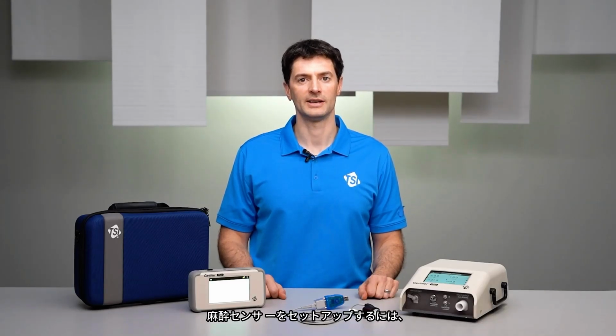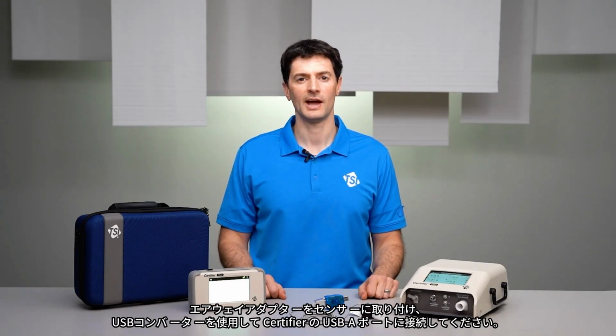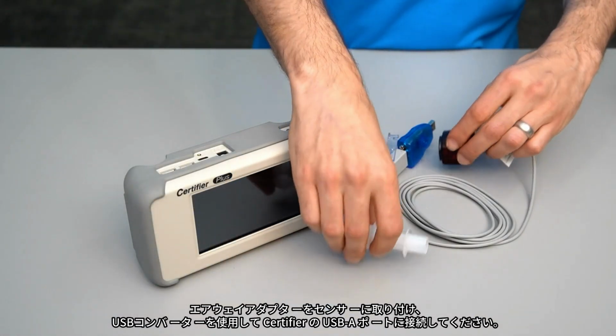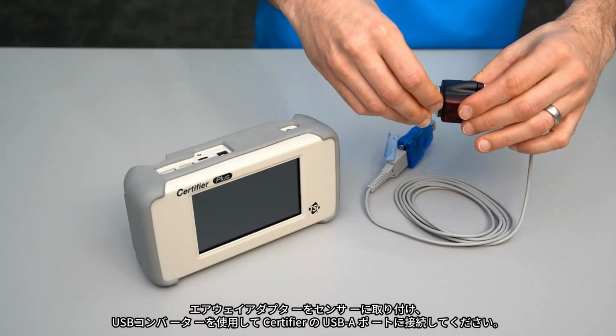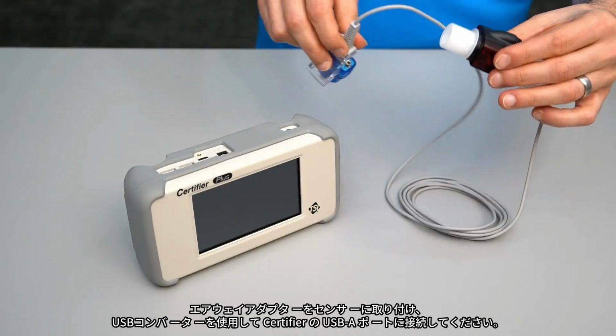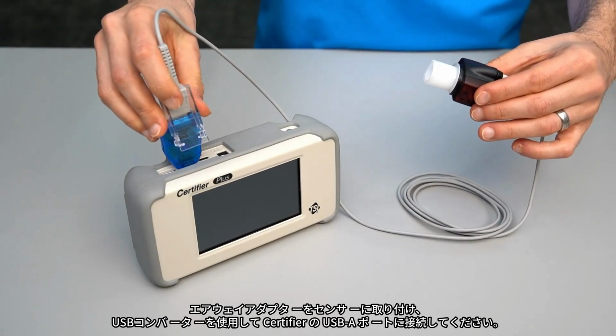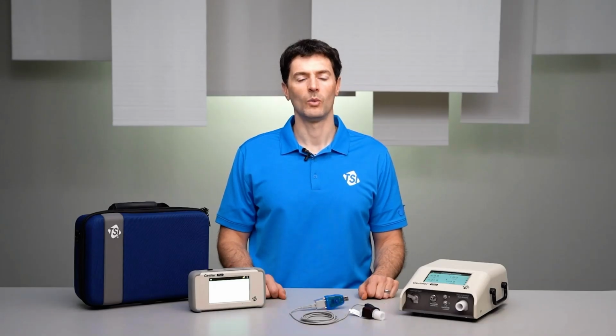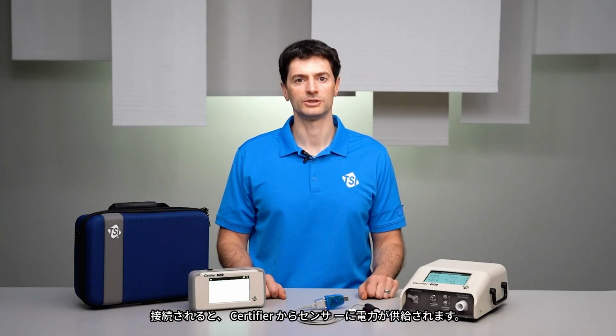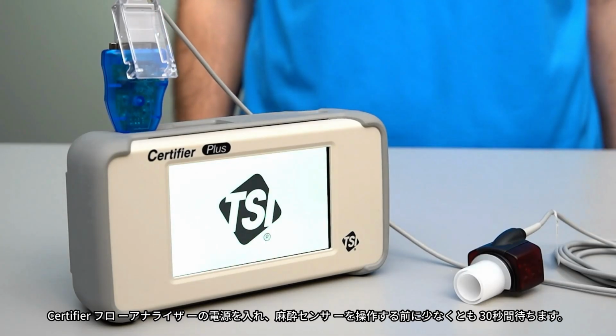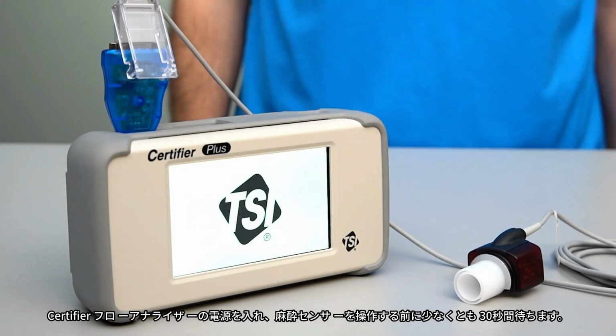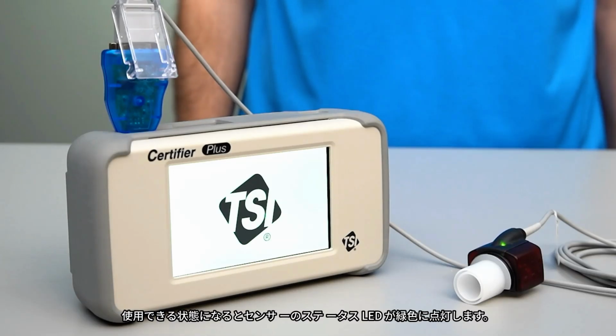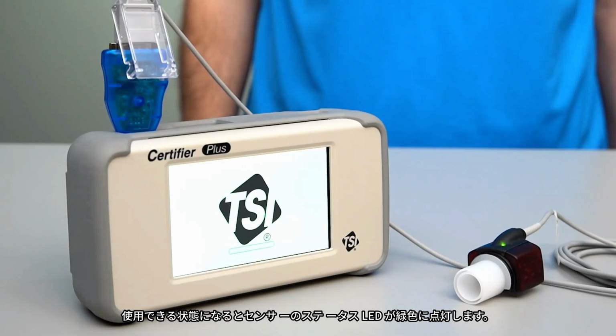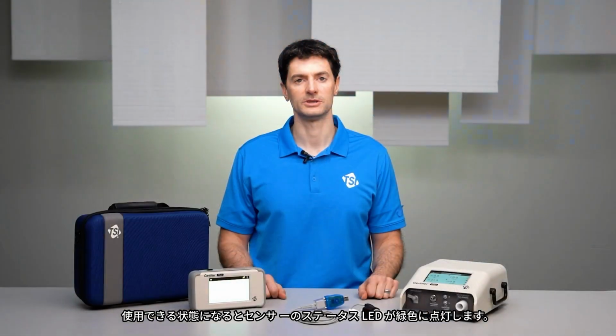To set up the anesthesia sensor, simply attach an airway adapter to the sensor and connect it by plugging the cable into a USB-A port on the Certifier instrument using the USB converter. Once connected, the Certifier will supply power to the sensor. Turn on the Certifier flow analyzer and wait a minimum of 30 seconds before operating the anesthesia sensor. The status LED on the sensor will illuminate green when it's ready for use.